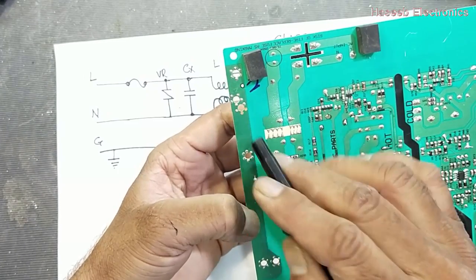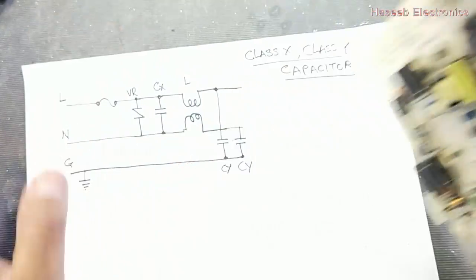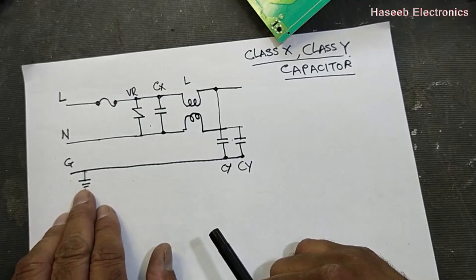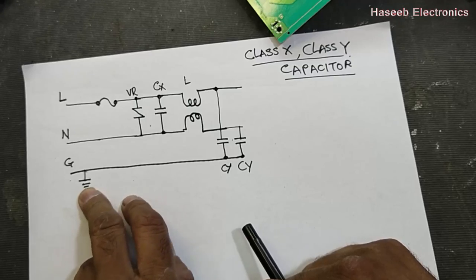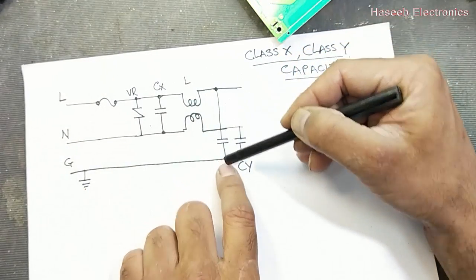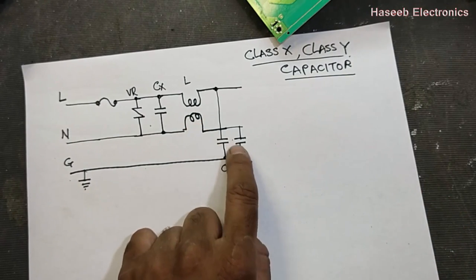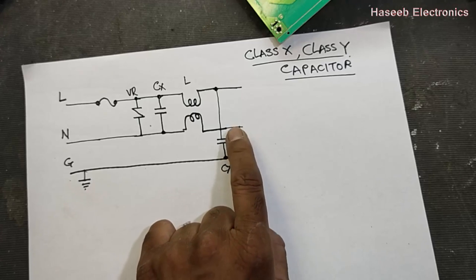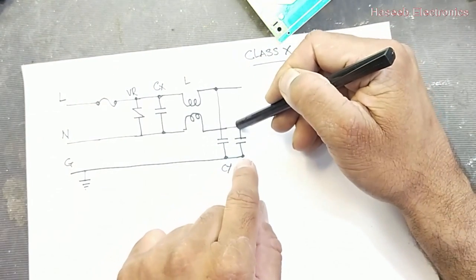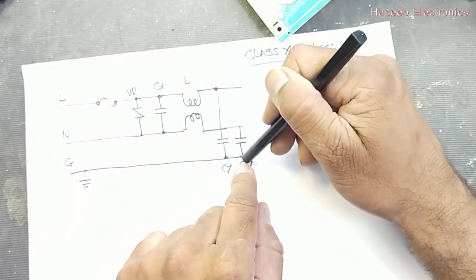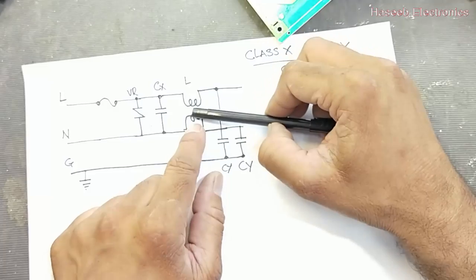In a three-wire system, these capacitors are connected to ground. So our line is connected to ground through this capacitor. Class Y capacitors are connected between line and ground, and neutral and ground. The X capacitor is connected between line and neutral, and here we have the inductor.